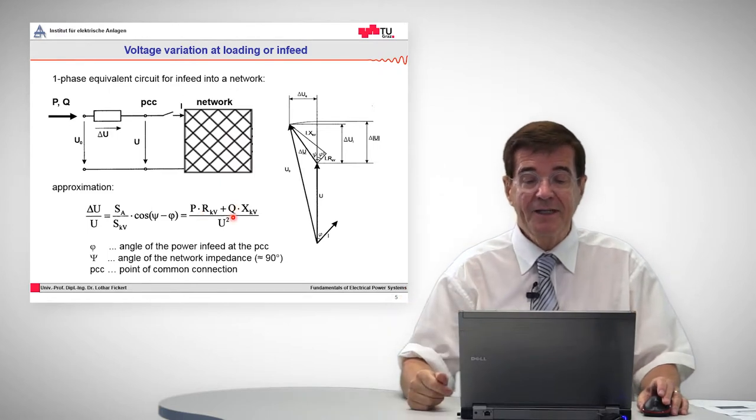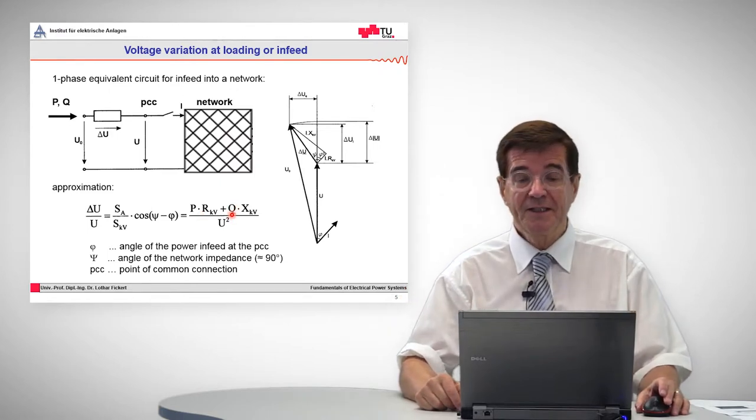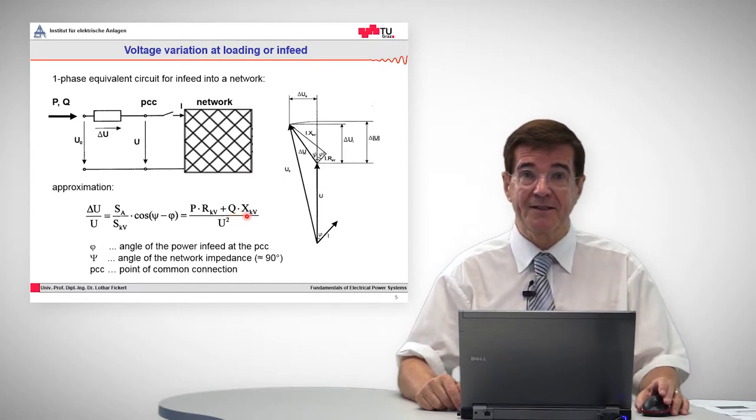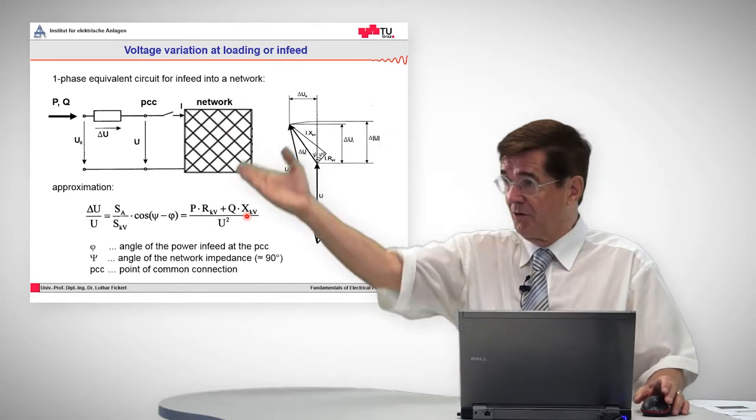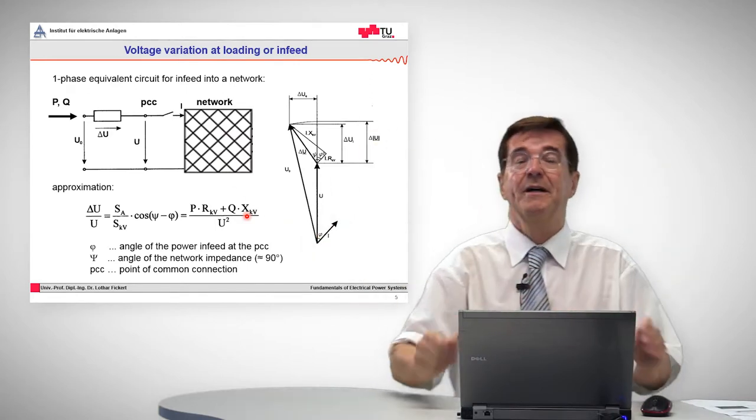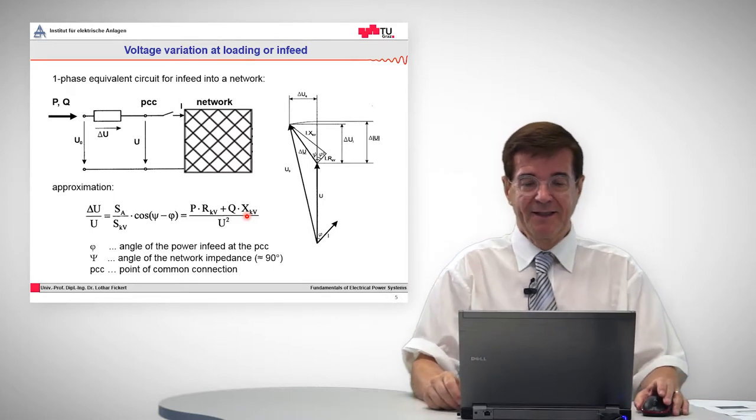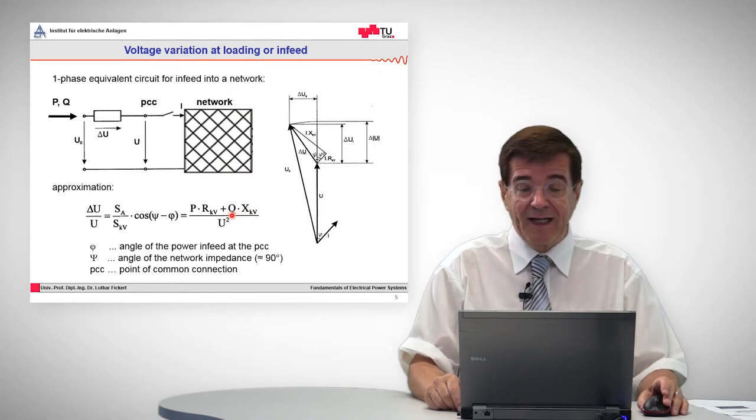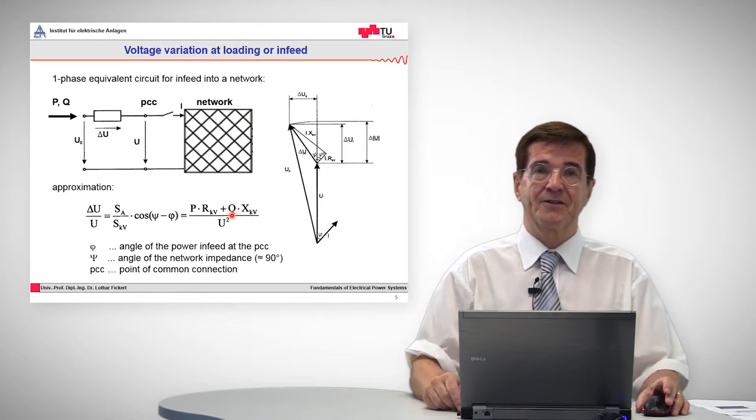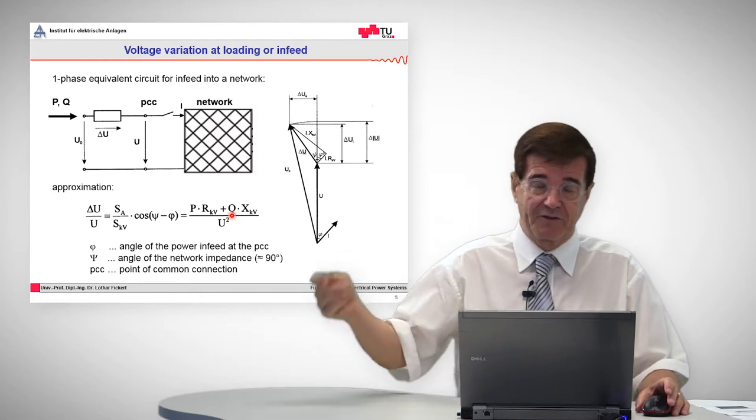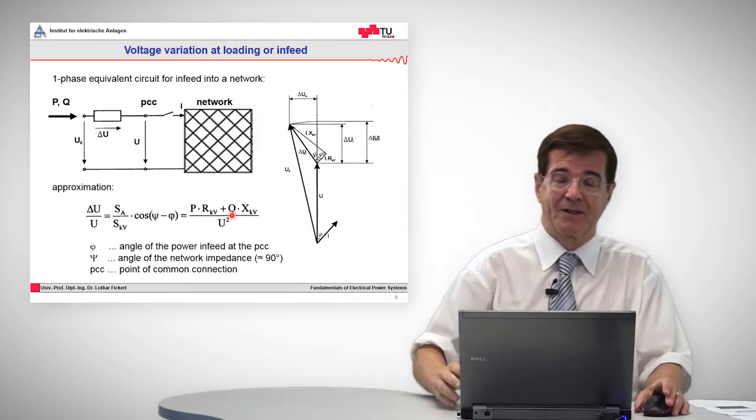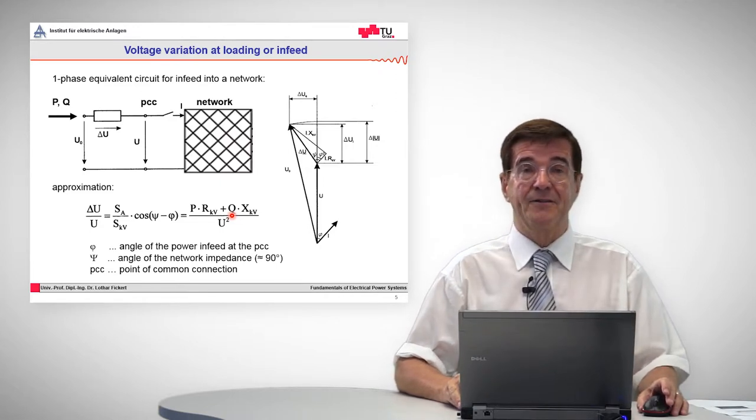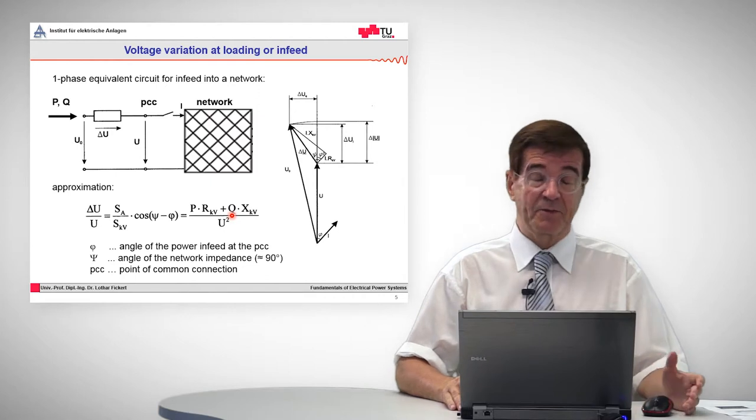On the other side, we need an electrical network, we need reactive power. This should be supplied from somewhere, and also this reactance is due to the loop impedance of the line. The current goes forth and back, and that is a loop, and a loop is a reactance. If the reactive power necessary to carry out the transportation and transformation of electrical power from one system voltage level to another is not provided by the distributed sources, it must be provided somewhere else.